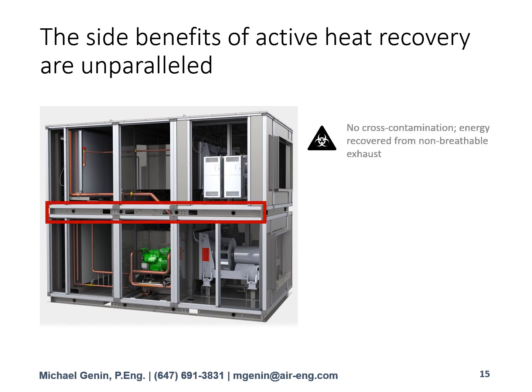extracted. So the first thing is no cross-contamination between the two air streams. The unit is designed for this, and because we don't have a heat rotor or other device where air streams are being switched, you can have a machine with no cross-contamination.